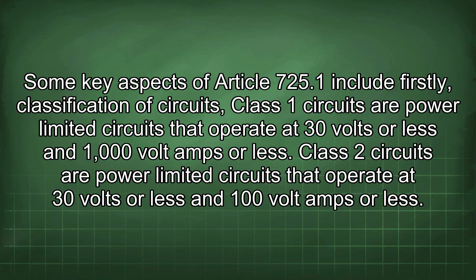Some key aspects of Article 725.1 include: firstly, classification of circuits. Class 1 circuits are power-limited circuits that operate at 30 volts or less and 1000 volt amps or less. Class 2 circuits are power-limited circuits that operate at 30 volts or less and 100 volt amps or less. Class 3 circuits are power-limited circuits that operate at 30 volts to 150 volts and are subject to additional safety requirements.